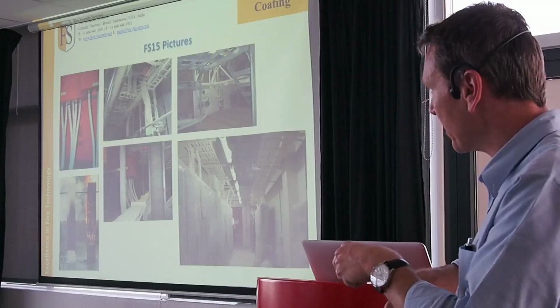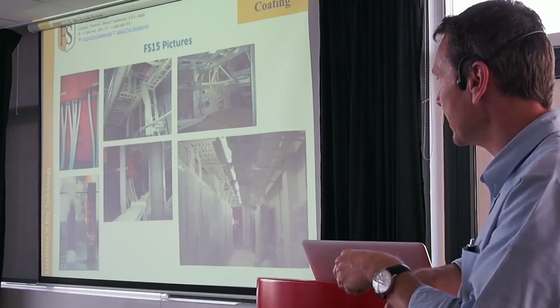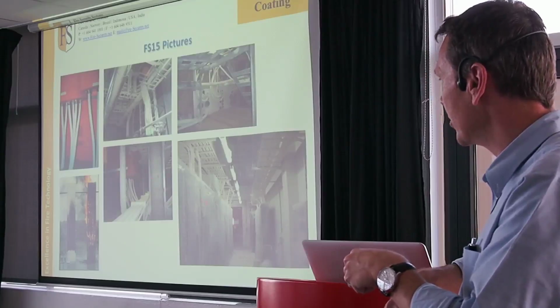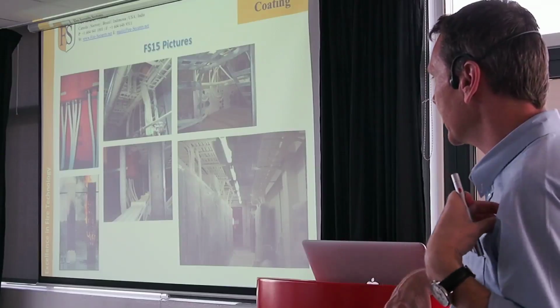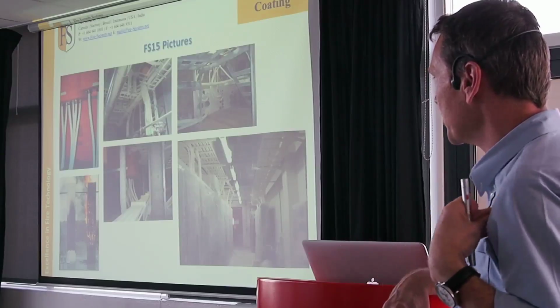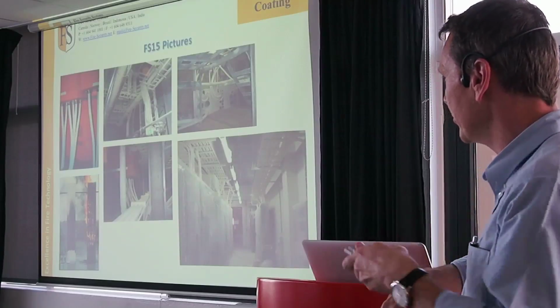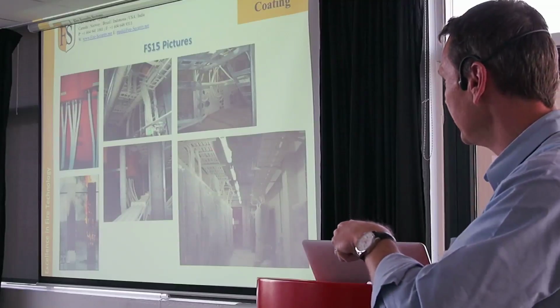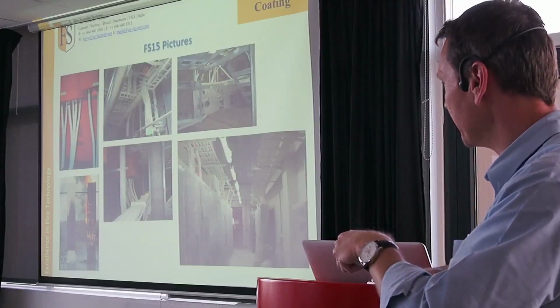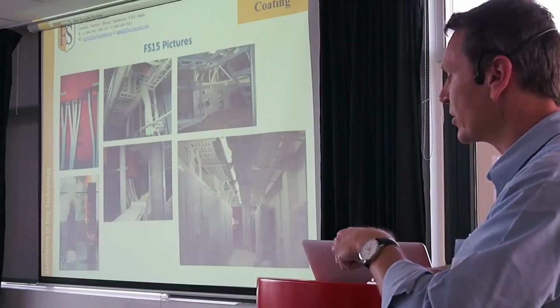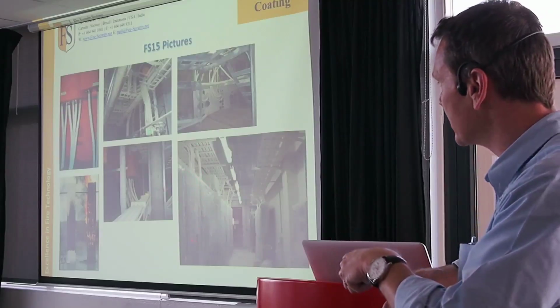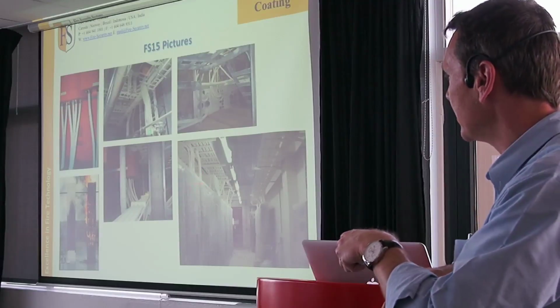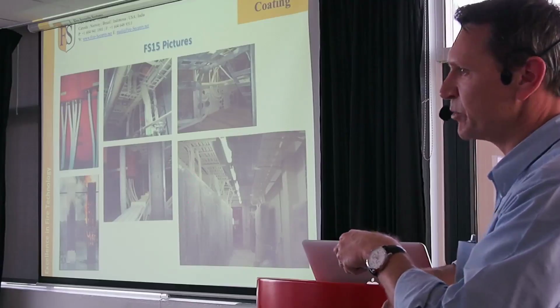Other typical applications are within basement areas, in cable galleries, and also in a switch room. So the cables are coated not only in the tray, but also the droppers coming down onto the switchgear, and also coating the glands. So if this facility lost this switchgear, it's a switchgear change, it's not a cable change.